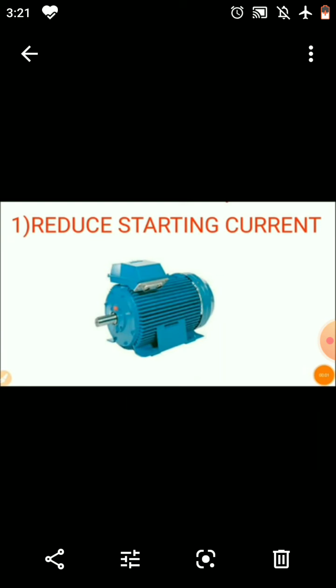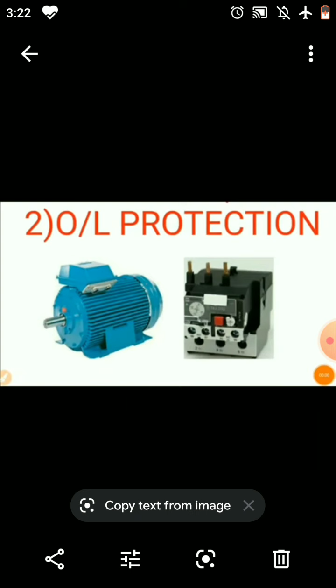Next, it provides the overload protection for the motors. The starters have an overload relay. Whenever the motor current exceeds the rated current, like if the motor is designed for 10 amps and the same 10 amps rating is set in the overload relay, if the current flows above 10 amps, the relay will trip the connection to the motor and the motor will be protected from any overload conditions.